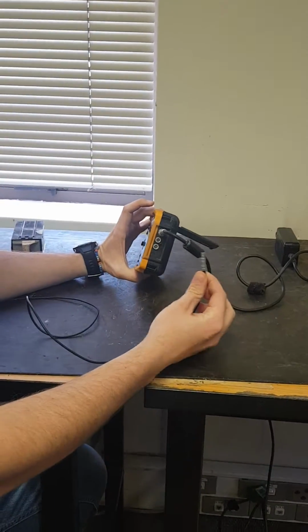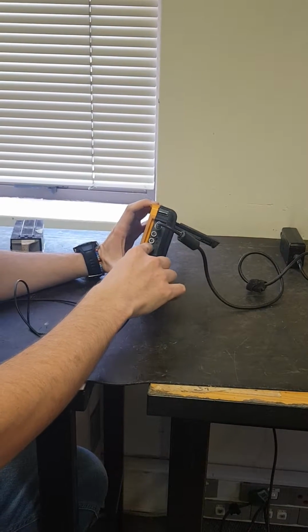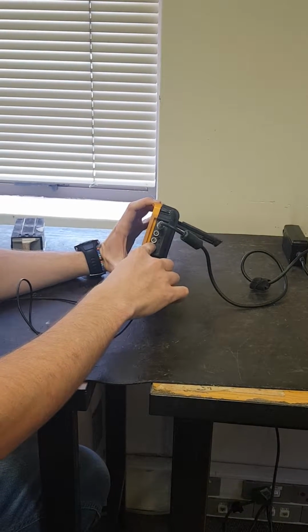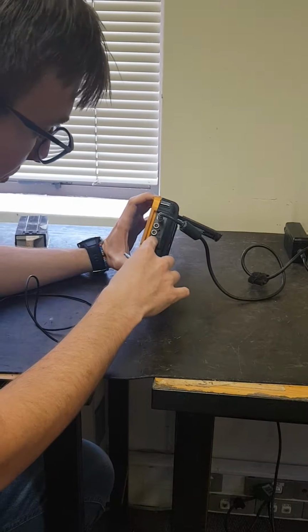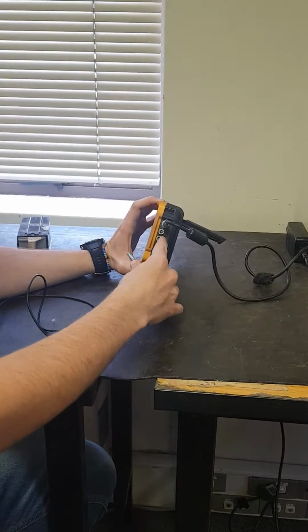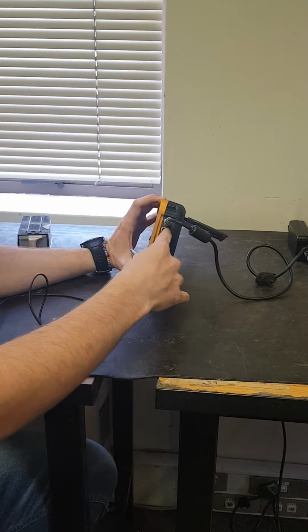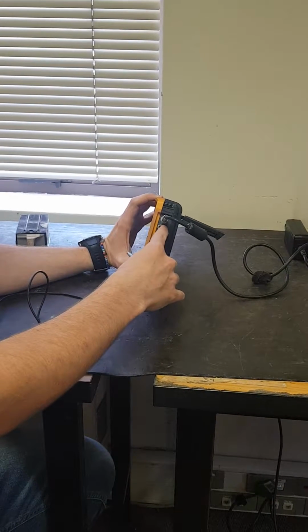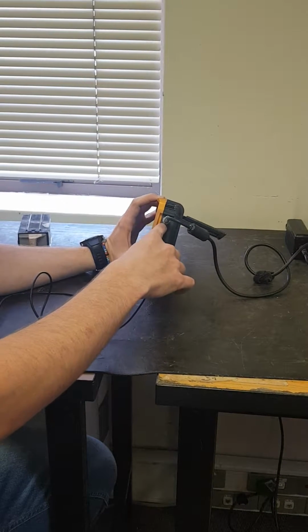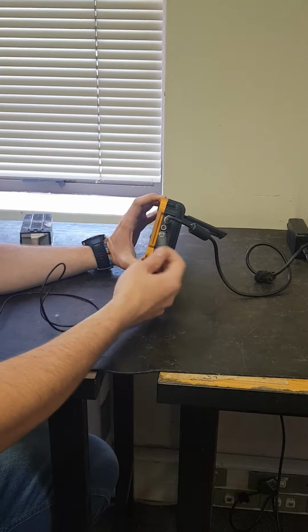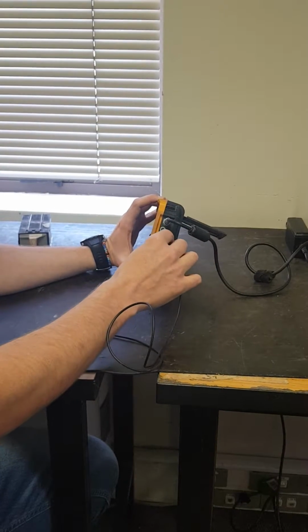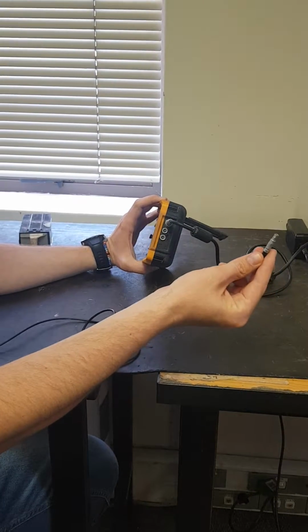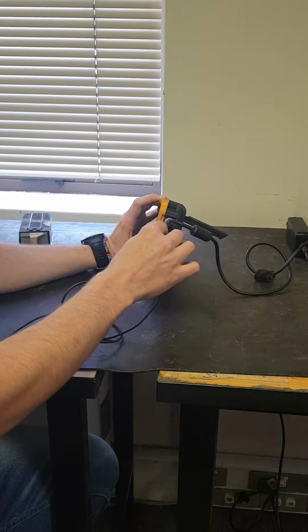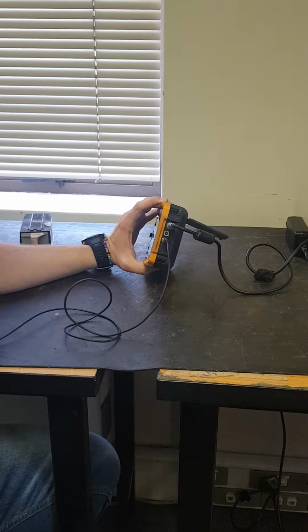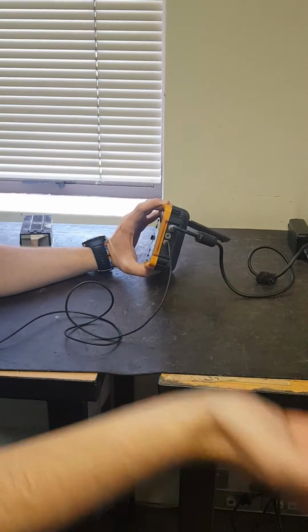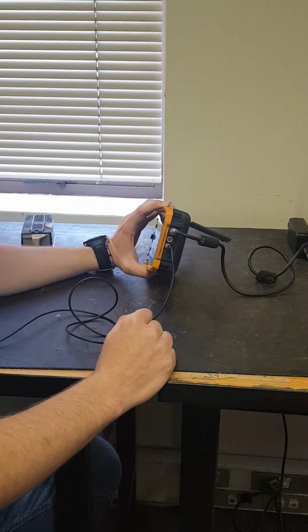So when we do the basic calibration of a 0 degree probe on the UT set, you're basically going to take your coax cable and insert it into the bottom slot there. The bottom slot has a send and receive function, and the top slot, if you look closely, will only have a receive function. You have two ports for your coax, since you can use a twin crystal probe. But in this case, we're only going to use a single crystal, so we want the port that sends and receives at the same time.